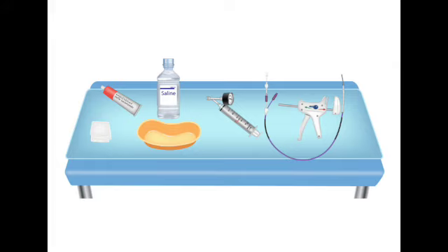But we're still not done. We haven't checked the catheter channel itself. Correct. And that is the second major air expulsion step. The catheter channel is just full of ambient air until we flush it. So how do we do that? To do this, we now switch the device to the deflation position, and this time, we angle the device down. So angle it down this time versus up for the syringe check. Why the difference? Well, when you angle it down and pump in deflation, you're actively sucking any air out of that catheter line and back into the syringe.